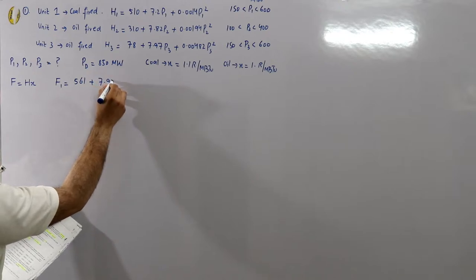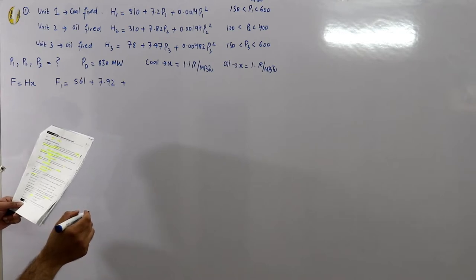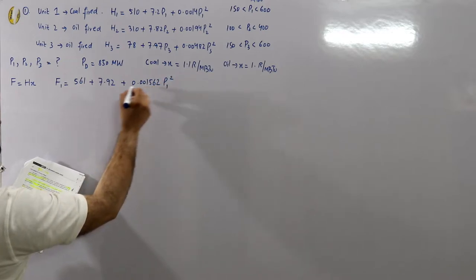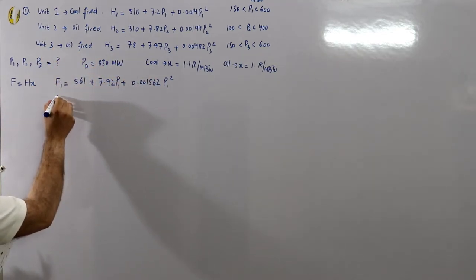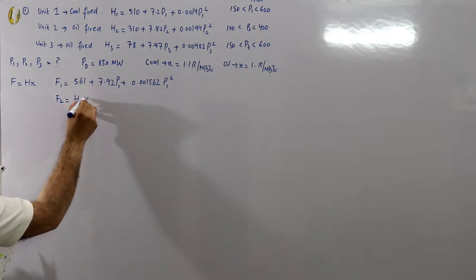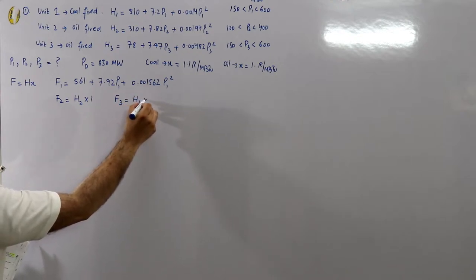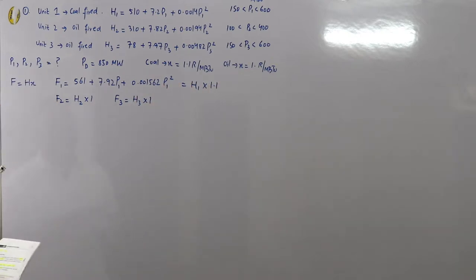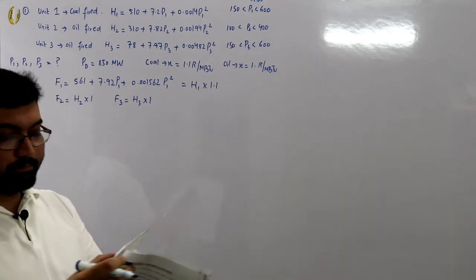For f1, this is coal-fired so multiply with 1.1: f1 = 561 + 7.92·p1 + 0.001562·p1². For f2 and f3, since x = 1 for oil, f2 = h2 and f3 = h3 unchanged. This is step number 0 — converting h into f.